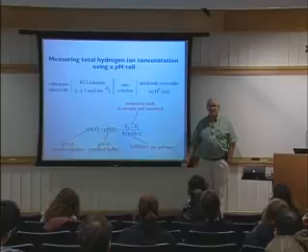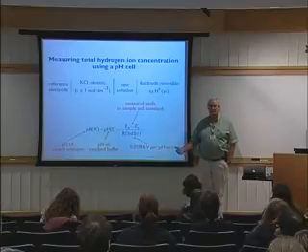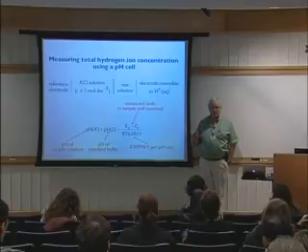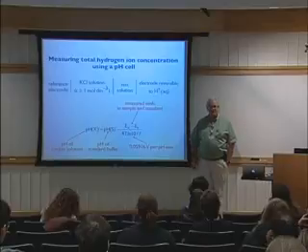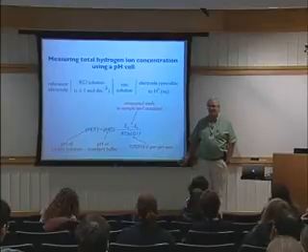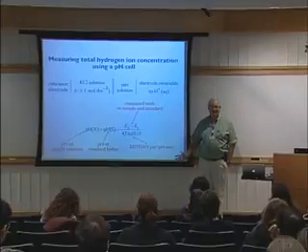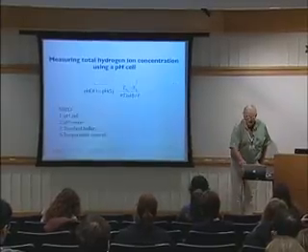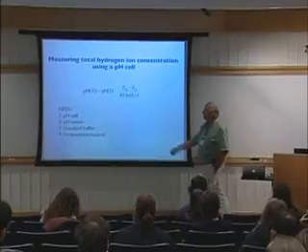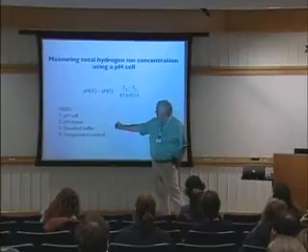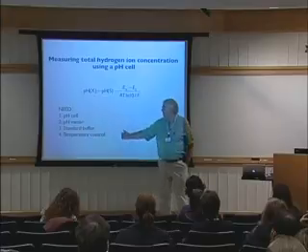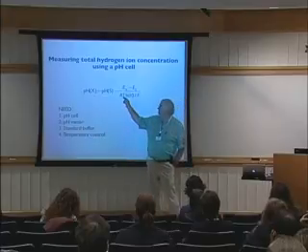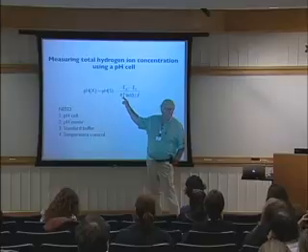And the answer is yes, if you're really sure those were pH 4 and 7. The very fact you say they're 4 and 7 suggests to me you don't really know, because to get exactly those values implies that corners have been cut to a large extent. So it becomes harder to know how well you've got it, and to get this, as I said, you have to have a pH cell, a pH meter, a standard buffer, oh, and temperature control, because you've got this term T here.